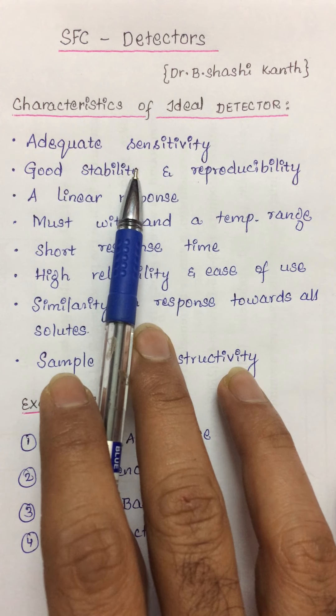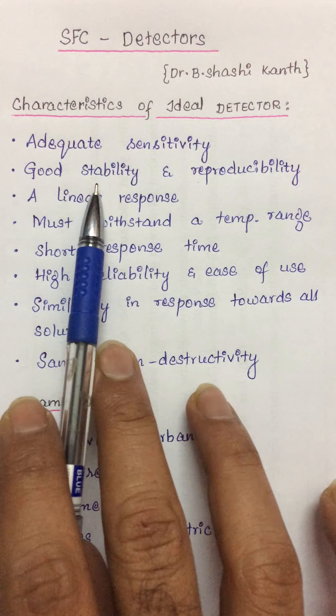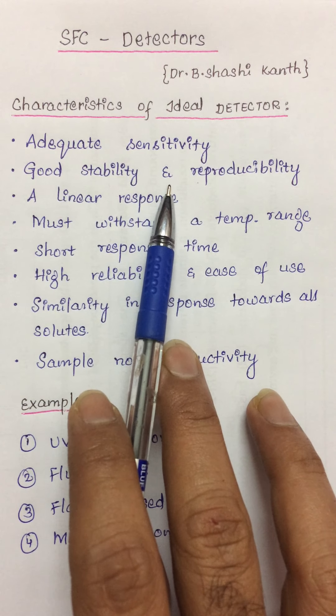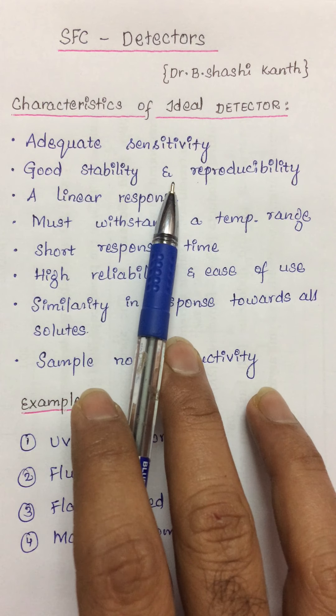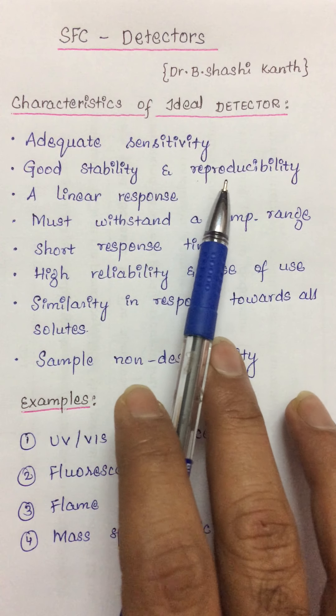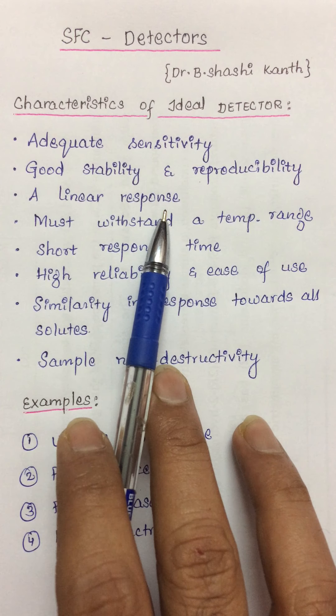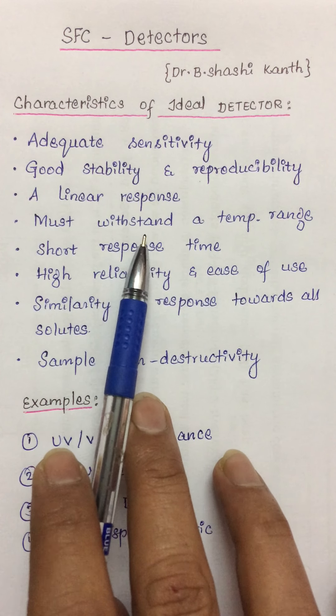The first characteristic is adequate sensitivity. These detectors must be able to detect even about nanogram to microgram solutes per second. Detectors should also have good stability and reproducibility — whether the experiment is done for the first time or repeated any number of times, the data produced must be the same. The response towards solutes should be linear and should extend over several orders of magnitude.